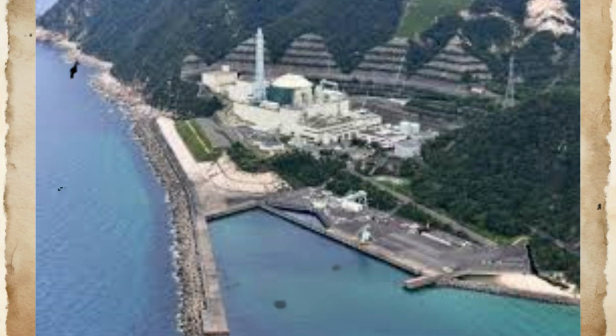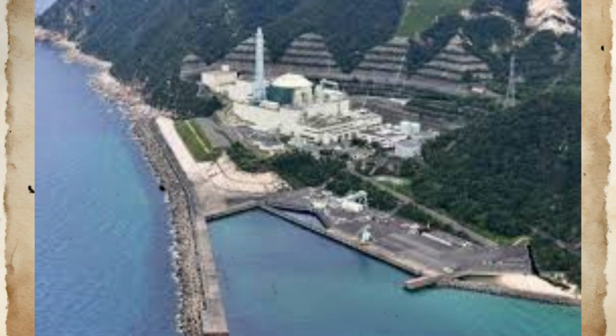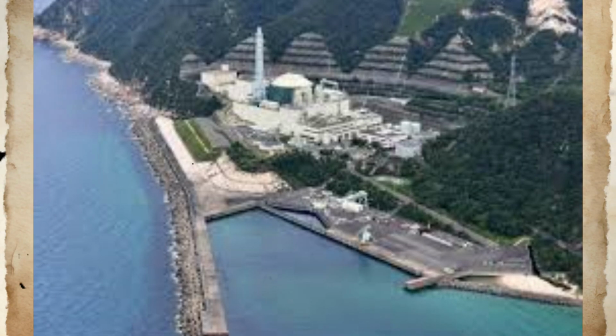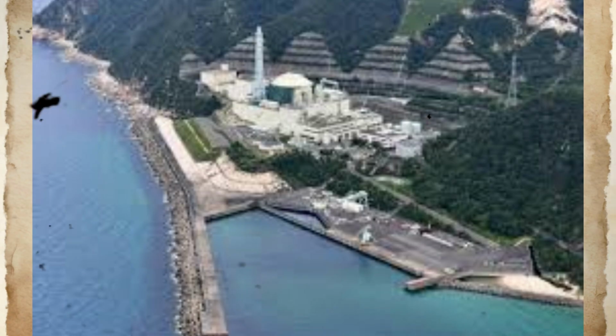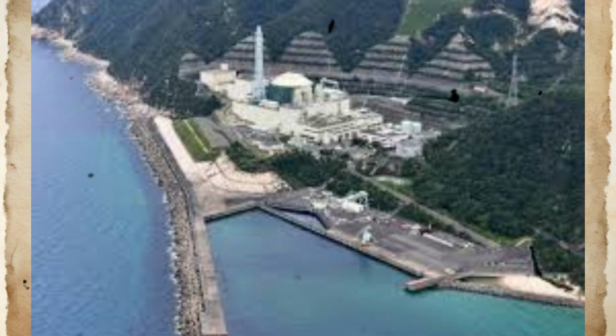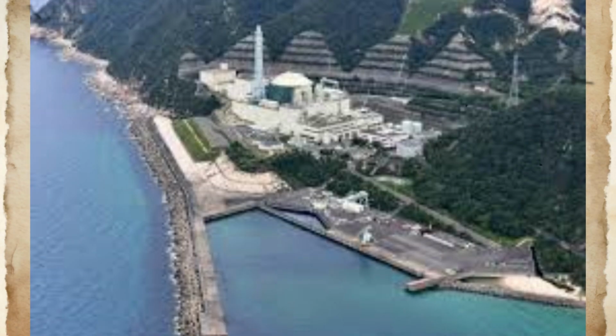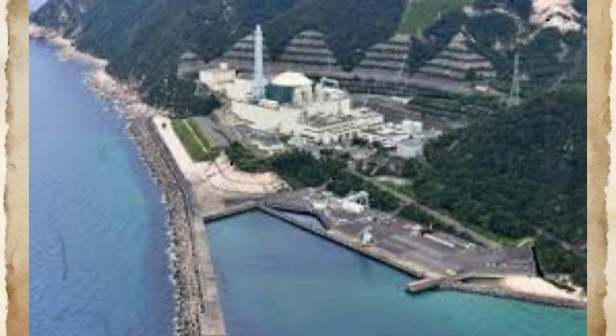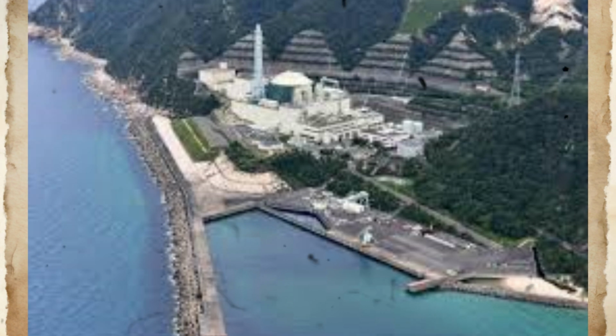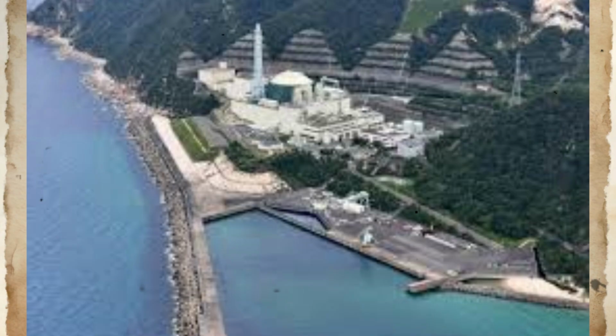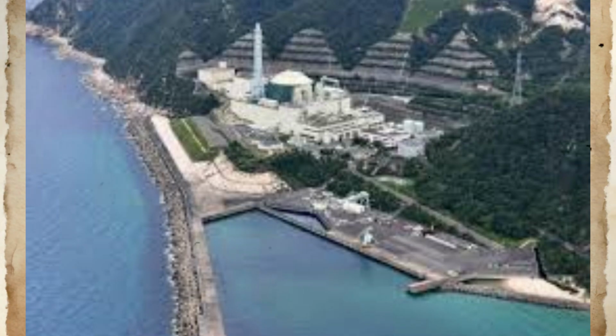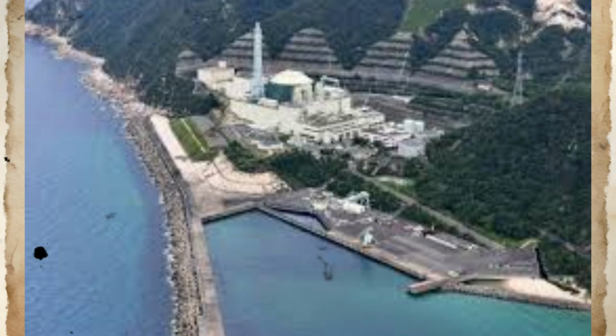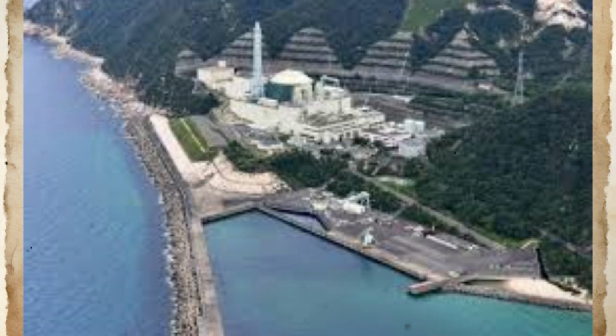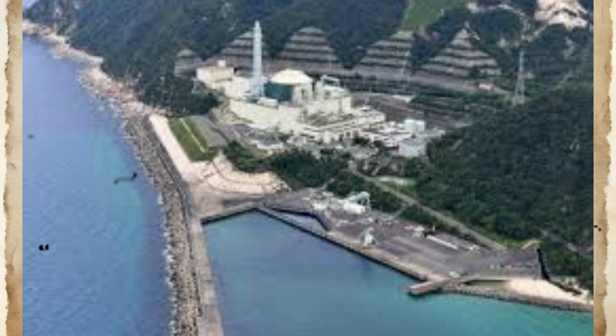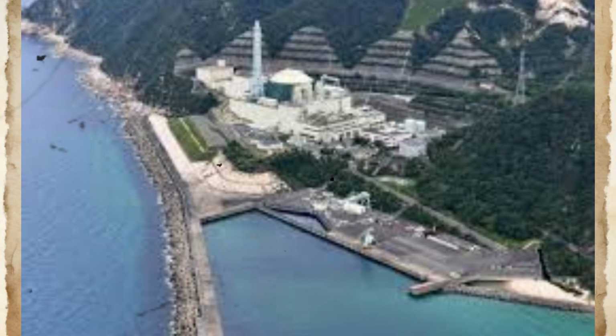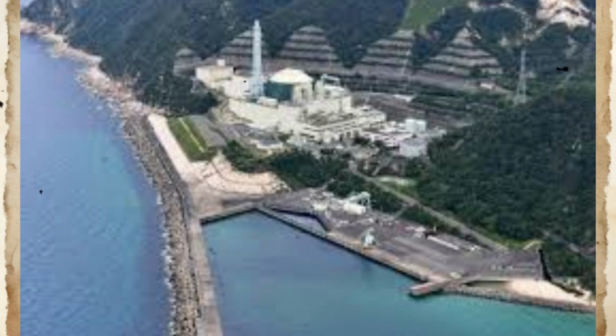Primary system pressure was maintained within normal ranges by the pressurizer system, which continued operating normally despite the secondary system disturbance. Secondary system pressure in the intact loops was maintained by normal pressure control systems operating at increased thermal loads. The auxiliary cooling systems provided essential backup heat removal capability that enabled successful management of the event. ACS operation demonstrated the effectiveness of design provisions for emergency heat removal and confirmed that adequate cooling capacity was available even with one complete heat transport loop unavailable.